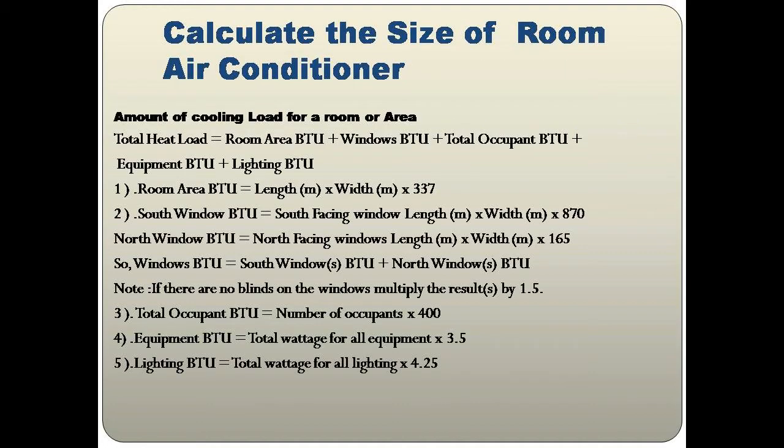For the calculation of the size of a room air conditioner, several parameters are involved. We need to calculate the total heat load in BTUs, then divide by 12,000 to get how many tons of refrigeration we need. As you can see on the screen, the formula is: Total Heat Load = Room Area BTU + Windows BTU + Total Occupants BTU + Equipment BTU + Lighting BTU.